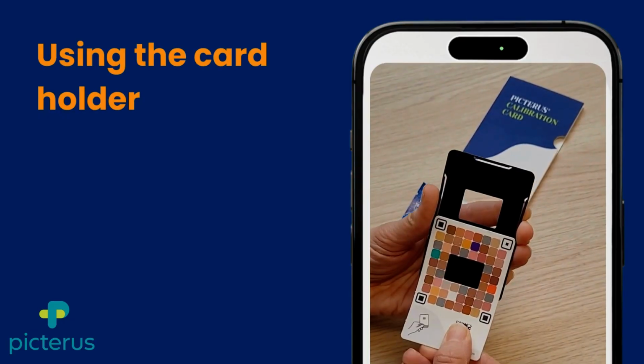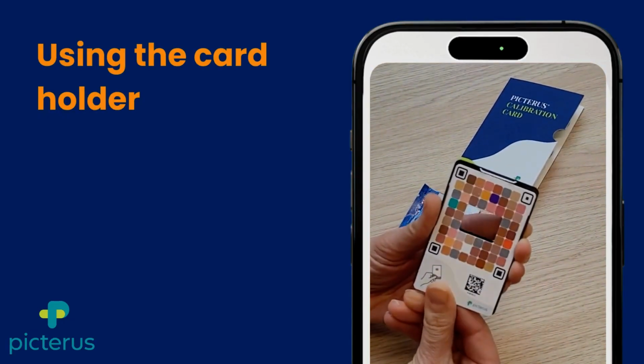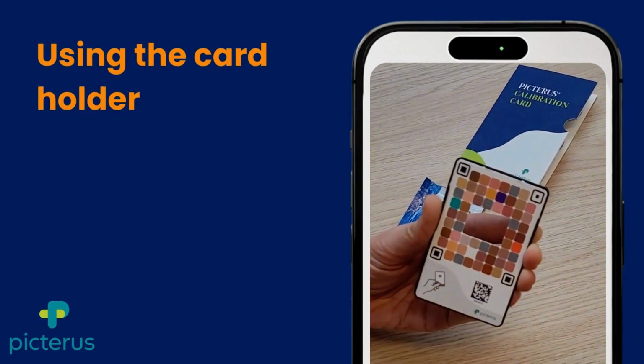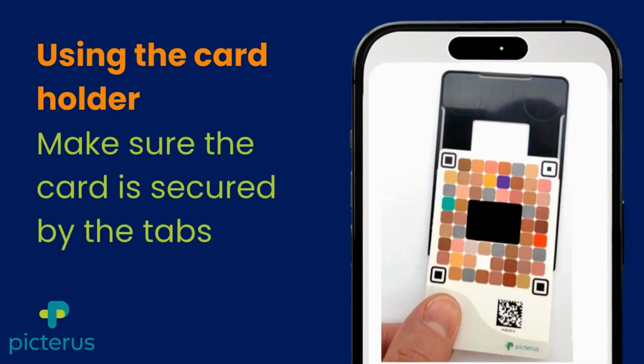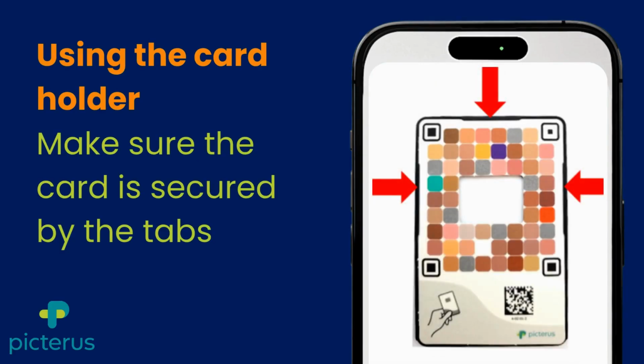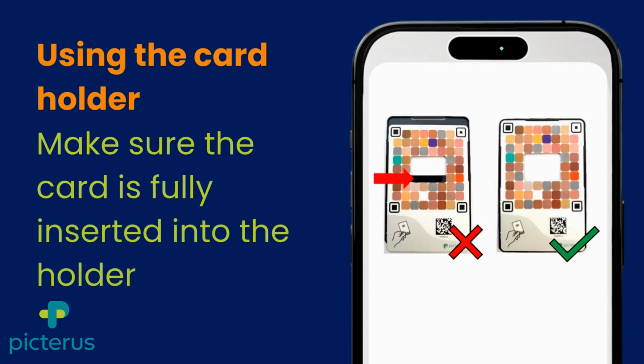The calibration card is inserted into the holder like this. Make sure you don't touch the color patches on the card. Make sure that the card is secured under the tabs on the holder. Check that the card is fully inserted. The hole in the calibration card should be aligned with the hole in the card holder.